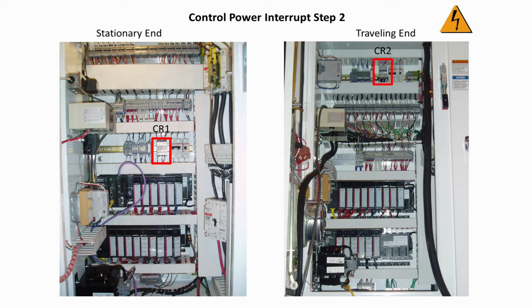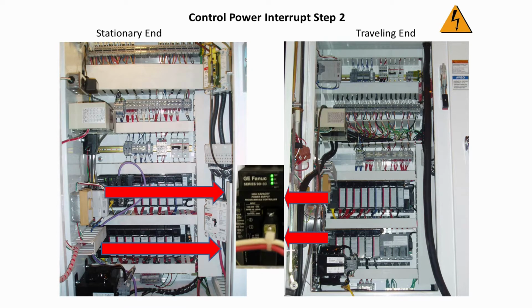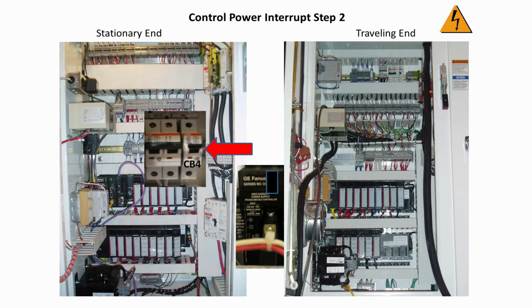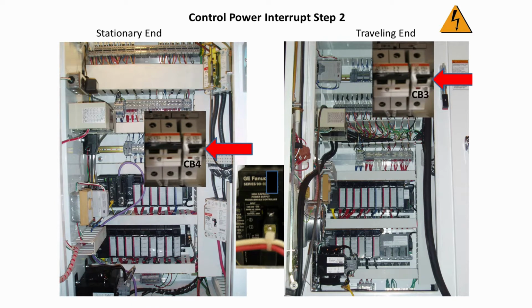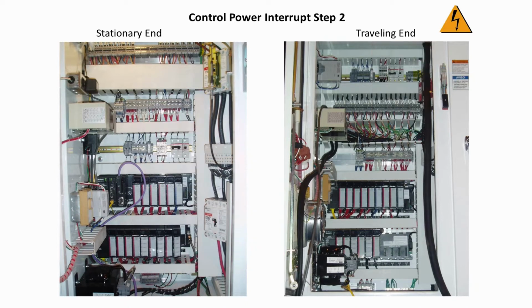Check number 1. With both the left-hand doors on the electrical panels on the stationary and traveling end open and the power on, look at the PLC power supplies in both racks on both ends. In both electrical panels, 3 lights should be on: Power, OK, and Run. If there are no lights on, check to see if the CB4 circuit breaker for the stationary end or the CB3 circuit breaker for the traveling end are tripped. If either one is tripped, reset the circuit breaker. If it trips again, go to Step 3. If it does not trip, the saw is ready to be placed back into production.